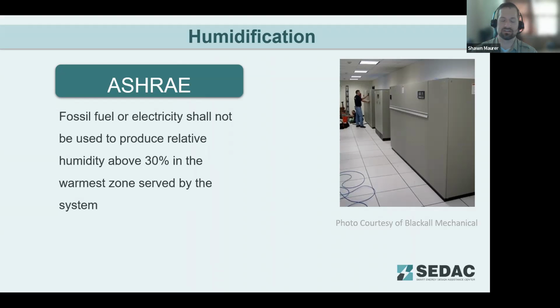Particular concern here is along windows and places where if you get above that 30% relative humidity, now you've got a condensation risk as well. So what we're looking at here is a bit of both energy minimization for that humidification system and building integrity control by limiting that moisture content to something that's reasonably expected not to create condensation on the coldest surfaces in your building.